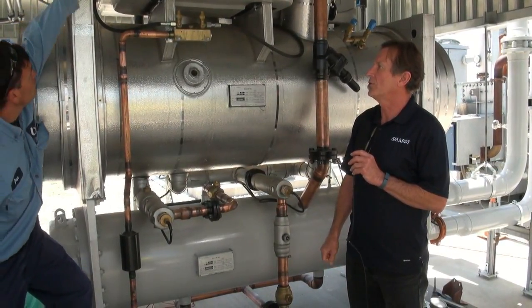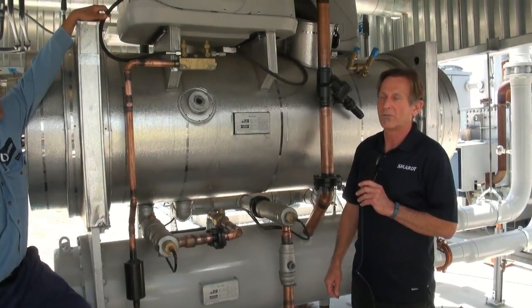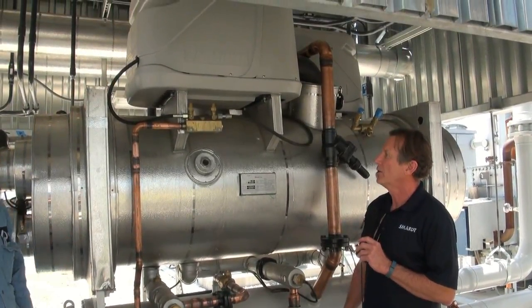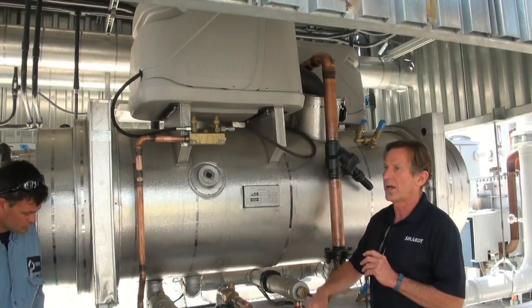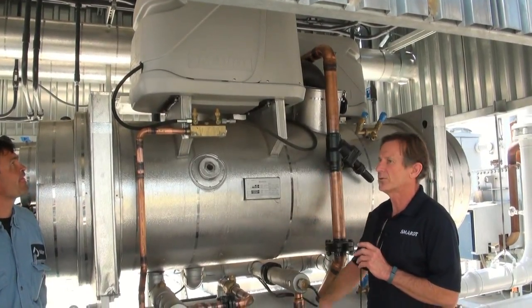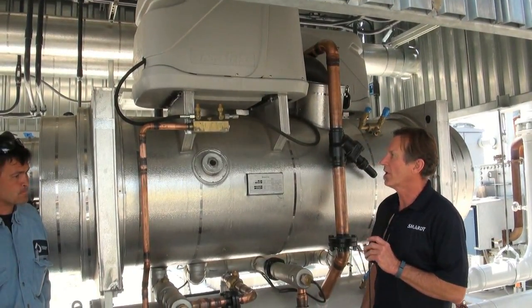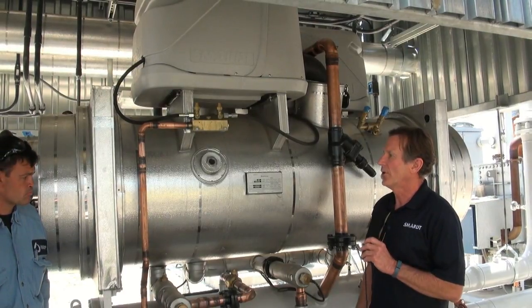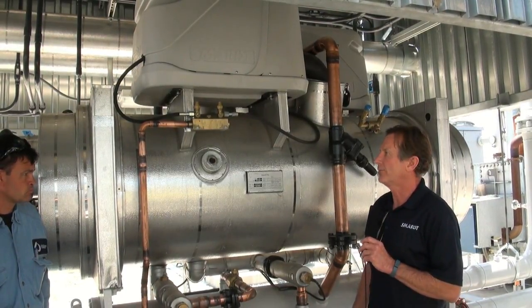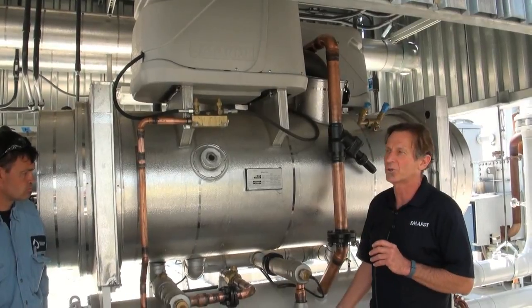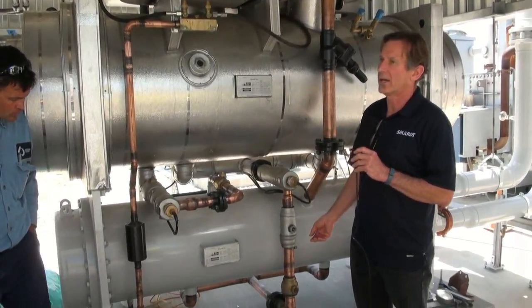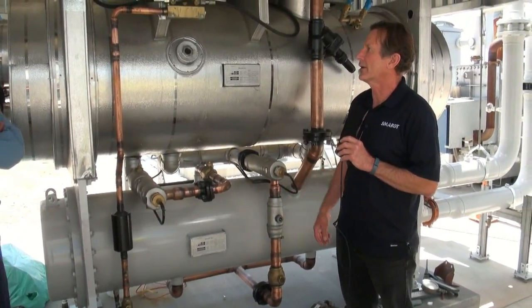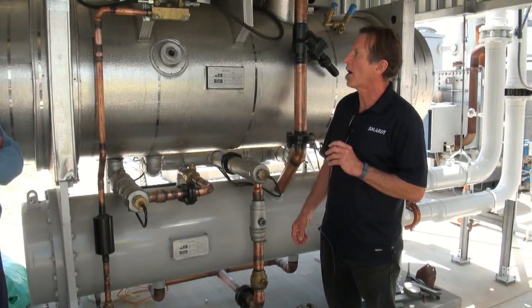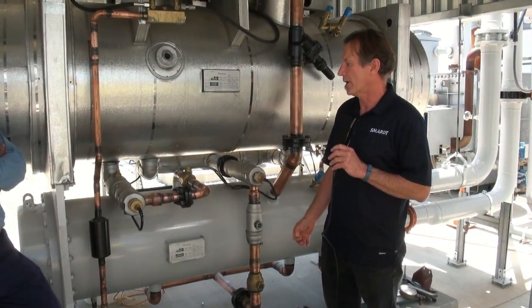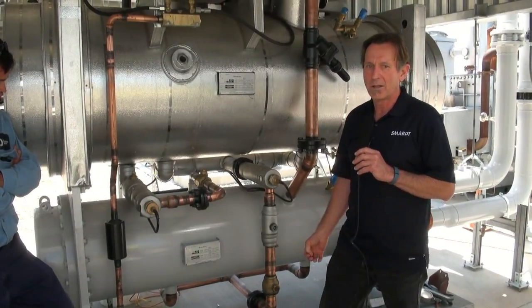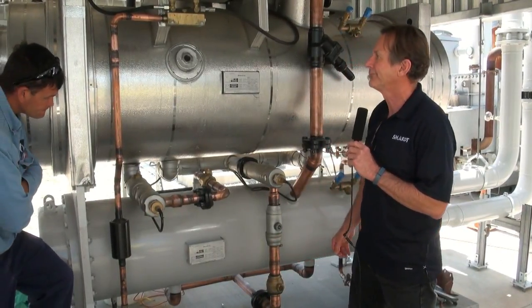If it's a very low load situation, the compressors are spinning at a very low RPM, you may see a little flash gas or a little bubbles in there, but don't be too concerned with that. It's more when you're under a higher load, not full load, but a higher load situation, where you're going to want to see that sight glass full. If you see it starting to bubble and flash, then there could be a problem with the chiller, either loss of refrigerant or loss of valve control.